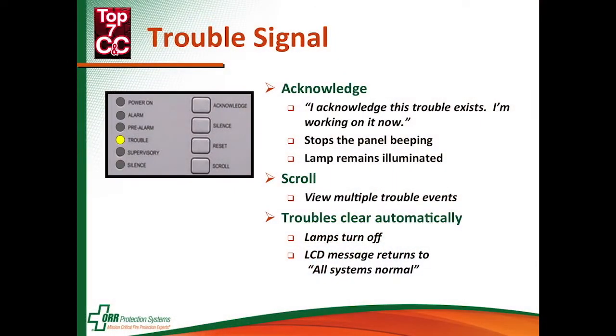What's important about troubles is when they're fixed, they clear automatically — so we don't have to reset the panel for a trouble. When we fix the problem, the trouble is going to automatically clear. And that's true for supervisory signals also. Alarms, now we have to reset. But troubles and supervisories, they clear once the offending condition is fixed.